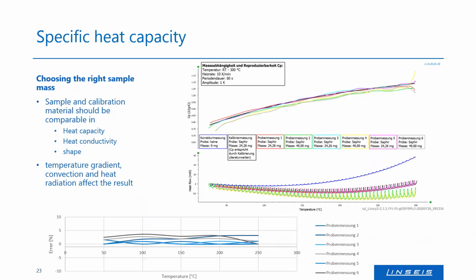Another investigation was the choice of the right sample mass, because this would also affect our result. So I've checked, okay, let's choose something between 25 and 50 milligrams. And what we can see here is that the deviation is around 3% error. But it is important: the heat capacity of your sample, the heat conductivity, and really important, the shape of your sample will affect the accuracy of your result here. Because the heat has to go through the crucible into the sample, the shape is pretty important.